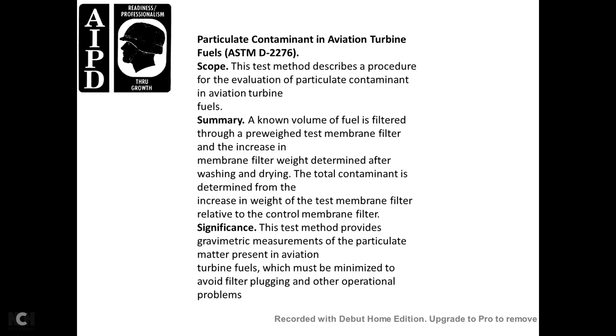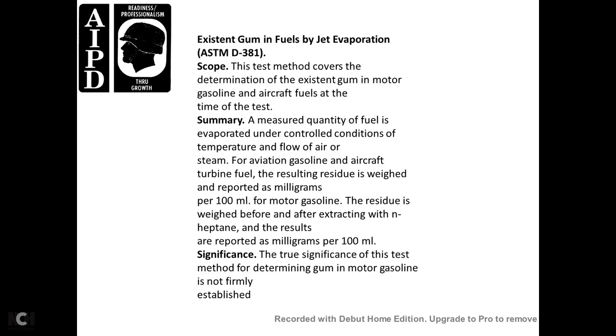Particulate Contamination — Aviation Turbine Fuels, ASTM D2276. Scope: describes the procedure for evaluating particulate matter in aviation turbine fuel. Summary: a known volume of fuel is filtered through a pre-weighed test membrane filter; the increase in the membrane filter weight, determined after washing and drying, gives total contamination relative to the control membrane filter. Significance: provides a gravimetric measurement of particulate matter in aviation turbine fuels which must be minimized to avoid filter plugging and other operational problems.